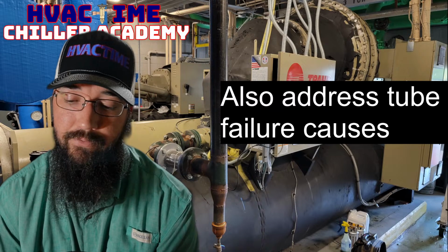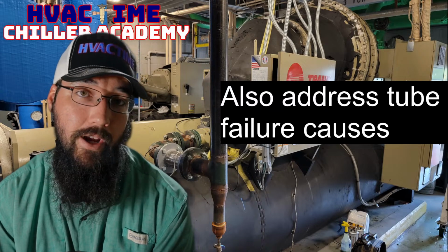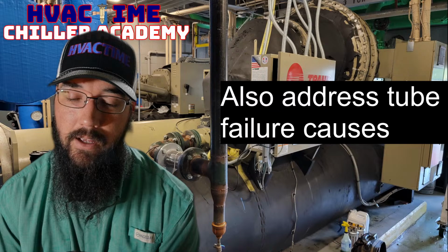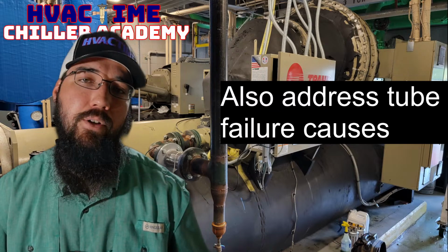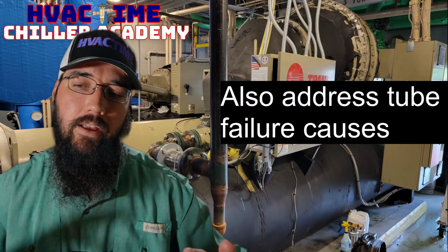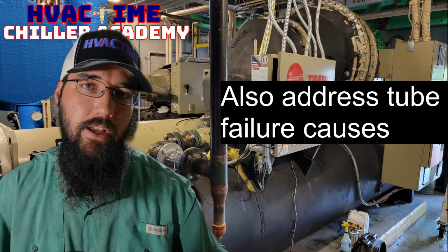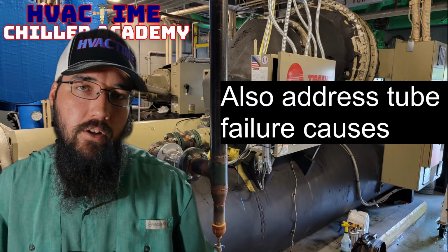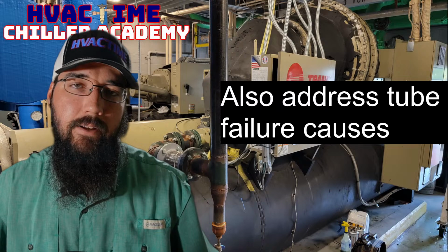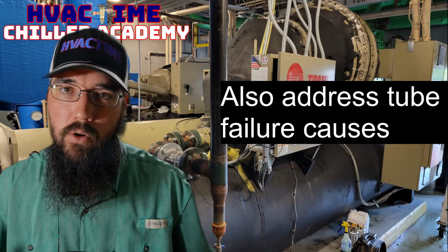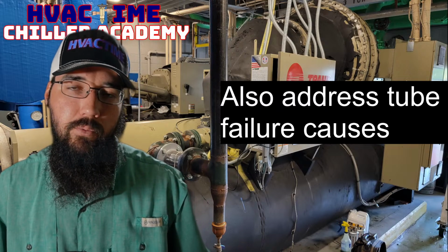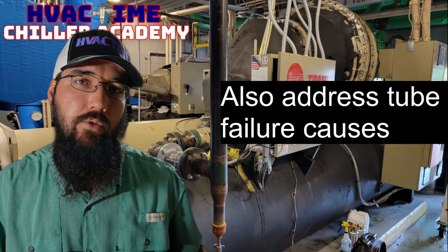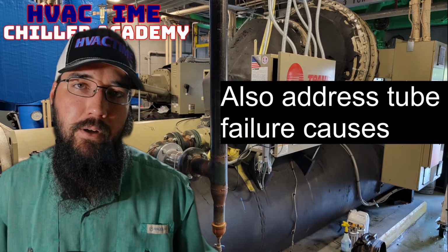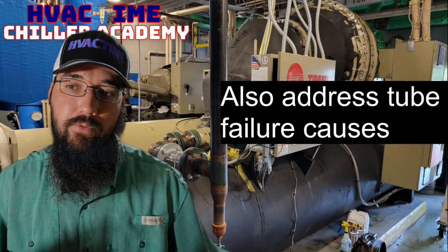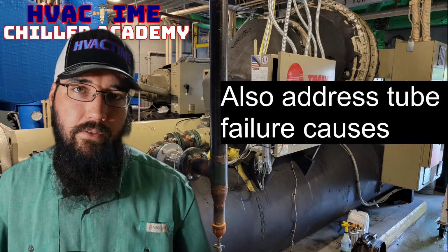None of our loops are designed for glycol. We typically don't drain our loops, or at least we used to not, because the down period was so short and we had enough insulation that we rarely got cold enough for long enough. Usually flowing water was more than adequate to protect our tubes in the winter time. When it got below freezing, we kicked the pumps on and flowed water for that period of time, and we never had an issue.